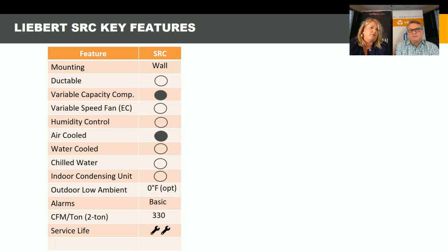Okay. Condensing unit. So the variable capacity, which I always think is cool to point out, is that it will ramp up and down according to the load, based on your load in the space. So if a customer has a really small load to start and they need to add more IT equipment, it's going to bump up to cool that load without you having to replace the air conditioner, right?